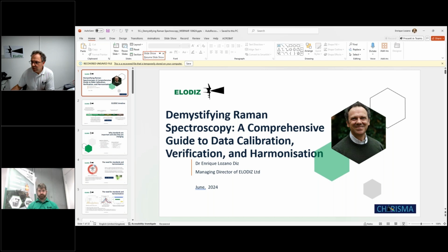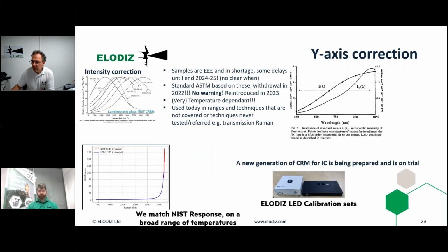Computer decided to strike. Okay, so some companies work with white light, which is perfectly fine. Some companies prefer to work with NIST standards, the National Institute of Standards and Technology, which produces a number of samples. But those NIST standards are very expensive and very rare. Sometimes they are not produced for years. So if you don't have one right now, you need to wait 1 or 2 years. And they are very temperature dependent.